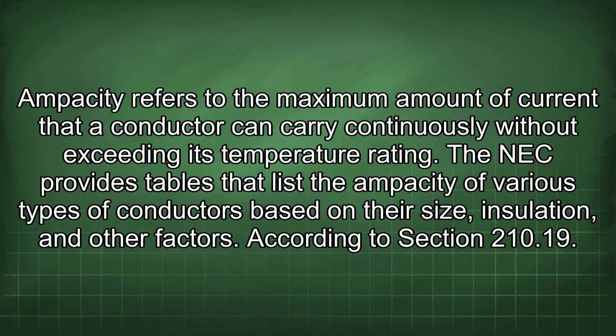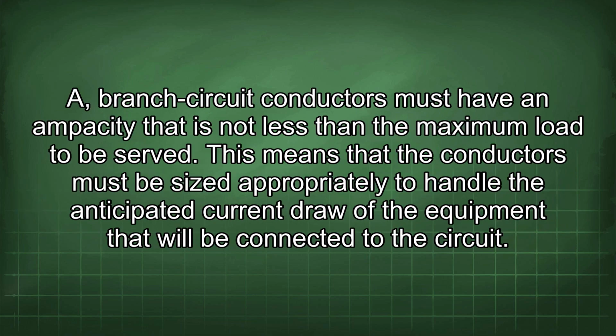Ampacity refers to the maximum amount of current that a conductor can carry continuously without exceeding its temperature rating. The NEC provides tables that list the ampacity of various types of conductors based on their size, insulation, and other factors. According to Section 210.19(A), branch circuit conductors must have an ampacity that is not less than the maximum load to be served. This means that the conductors must be sized appropriately to handle the anticipated current draw of the equipment that will be connected to the circuit.